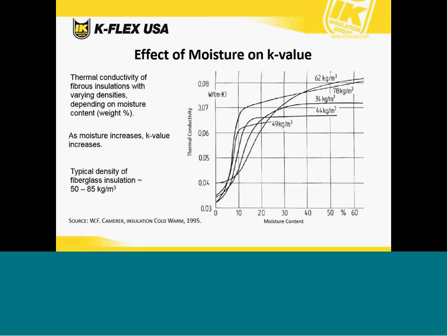I pointed out the K of water in the previous slide because it has a pretty profound effect on insulation. The value of 4 for water is about 16 times greater than your typical insulation K value, which means water is more of a conductor than an insulator. The thermal conductivity will increase as the moisture content of the insulation material increases. Here you can see the moisture content of a fibrous insulation and the resulting thermal conductivity as that moisture content increases. The chart shows that as moisture content increases, the K value increases fairly quickly. It's almost exponential, so you don't need a lot of moisture to degrade the performance of an insulating material.